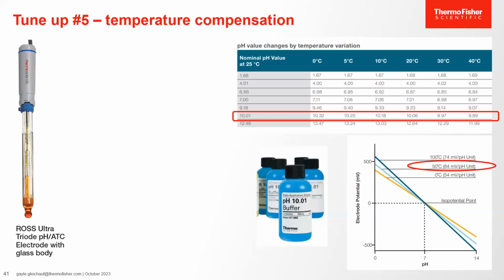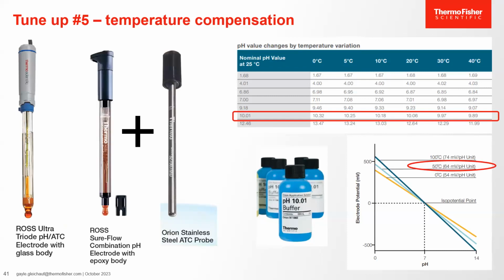We can use either a triode electrode or an ATC with a pH electrode. These will ensure proper pH temperature compensation. When using a temperature sensor with a pH electrode and an Orion meter, during calibration, the meter will automatically assign the correct known value of the buffer at the measured temperature. When the sample temperature differs from the calibration temperature, the Orion meter uses the temperature data from the sensor to compensate the calibration slope with a temperature change. In these ways, temperature compensation ensures that pH readings are accurate no matter what temperature the standards or the samples are at.